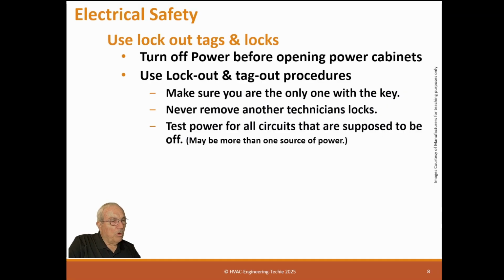Test power for all circuits that are supposed to be off. There may be more than one power source, and if you're at the breaker, you won't know that. You can only know that if you go to the machine. So always assume that you need to test it. Don't assume it's off. You need to actually test it.